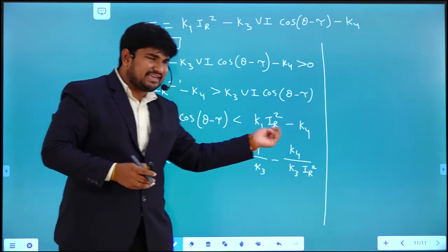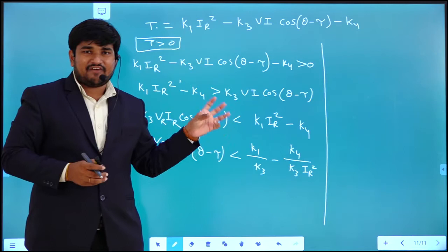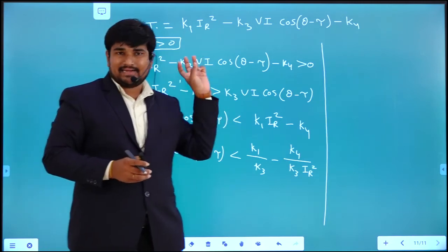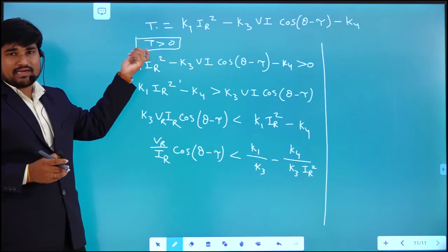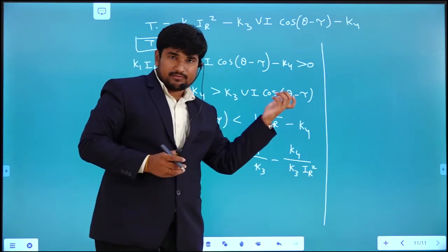In the previous session also we discussed that this spring restraining quantity is only effective in case of lower currents, right? But I am finding this positive torque, that means trip signal, during fault condition, that means the amount of current will be more, right?